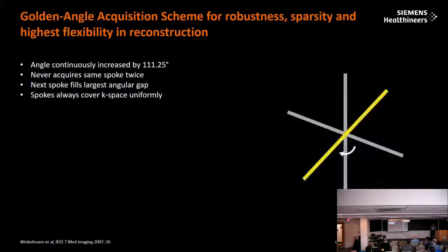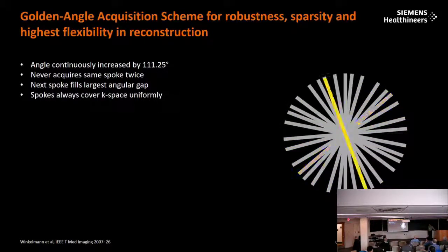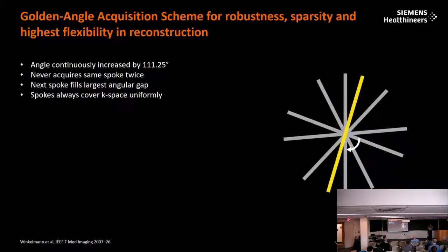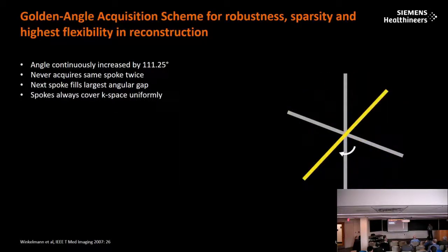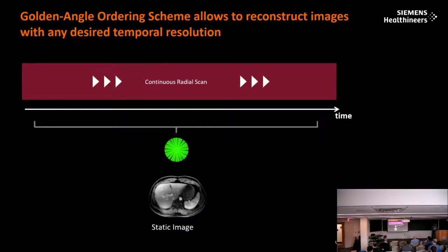This golden ratio radial has a specific property that the angle between 2 successive spokes is 1 over the golden ratio. And that essentially guarantees that no matter how you bin those data, you are always going to be reasonably close to uniformly covering the angular space in your K-space. So that means that you scan those data, and then a posteriori, you can decide how you reconstruct it. For example, you can do 1 single static reconstruction for everything. That is important because that is an image that you can show to the technologist at the scanner so that he can quickly check that the field of view is correct, the image was correctly acquired. So once you have that, you can let your patient go, and you can figure out how to get the final clinical images later.